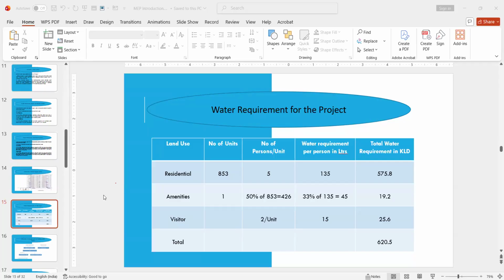Now amenities, meaning clubhouses. For clubhouses, what we usually do for the number of flats, for example if it is 853 flats, we consider 50% of 853, so 426 comes. And water requirement per person reduces to 45 liters only for clubhouses, because you are not there for 24 hours, maybe 2 to 5 hours maximum. So with 1 into 426 into 45, it comes to 19.2 KLD.